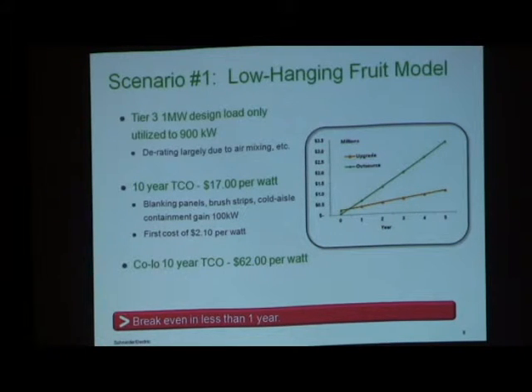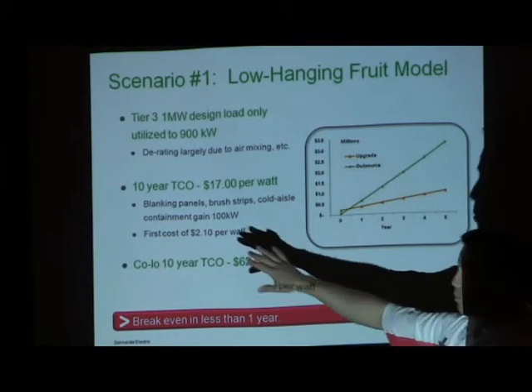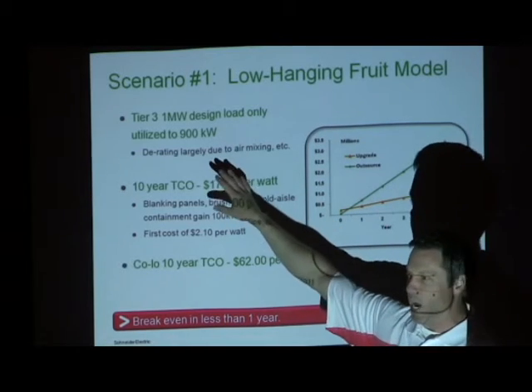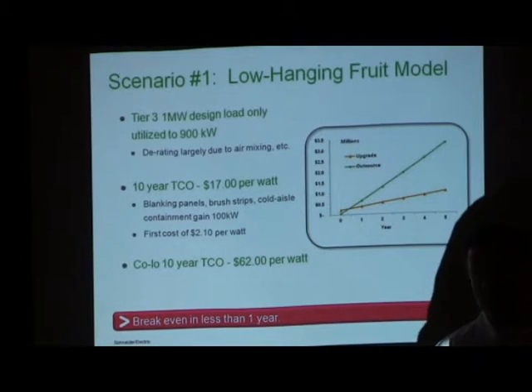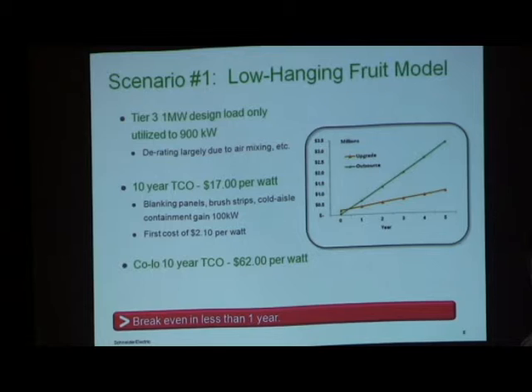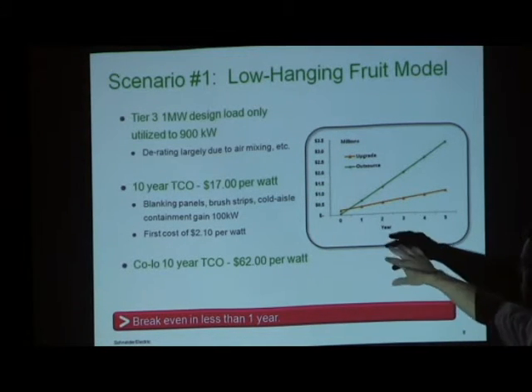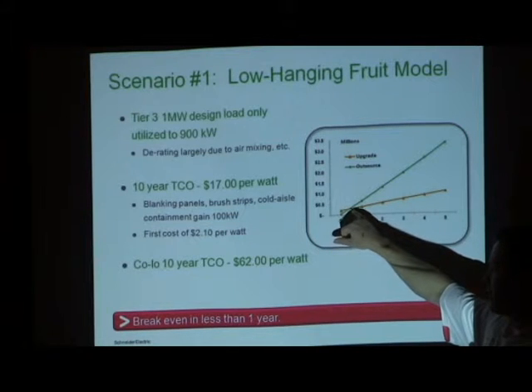So in this instance, it's showing that if we do just the blanking panels and brush strips, we gain that extra 100 kilowatts in cooling that we lost because of derating, because of that air mixing, basically meaning we have stranded cooling capacity. We're seeing here that the break-even point is basically less than a year.